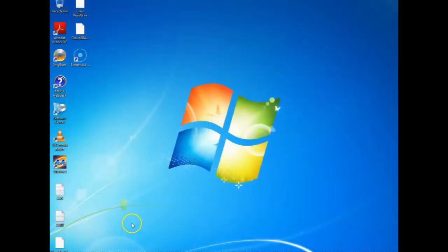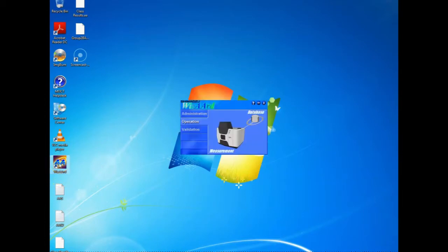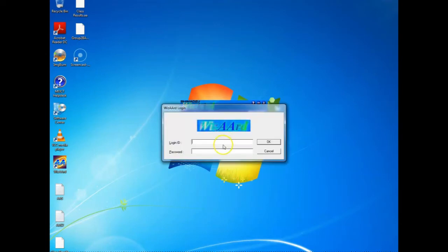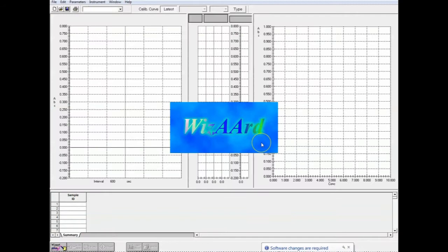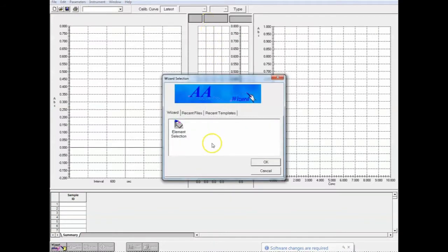The software for the atomic absorption unit is pre-installed on the computer that's attached to the unit. It's this icon right here. It's called AA Wizard, with two A's. When we're ready to start, we just click on the image of the instrument itself. We've set the login just to admin with no password, and then our software will open up. The nice thing about this software is it has a wizard that takes us through the entire setup. It gives us lots of messages and things to check as we go through, so it's really straightforward and fairly user-friendly. The first thing we want to do is choose which element we are going to be analyzing.